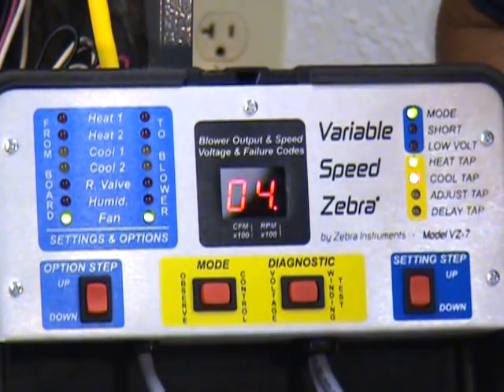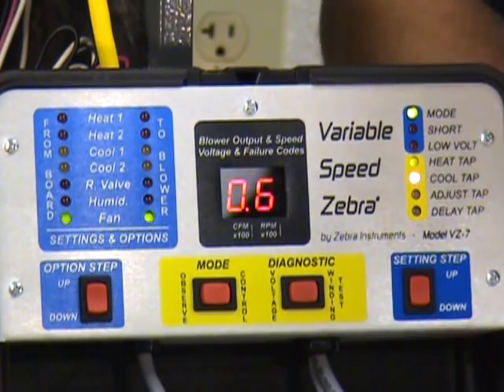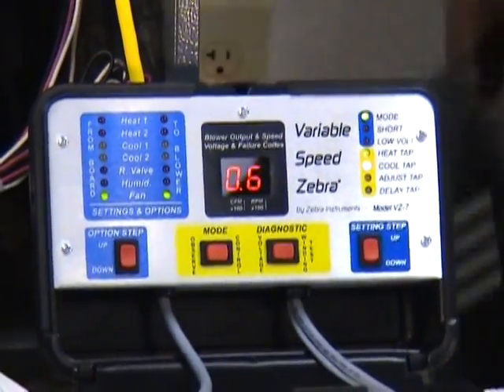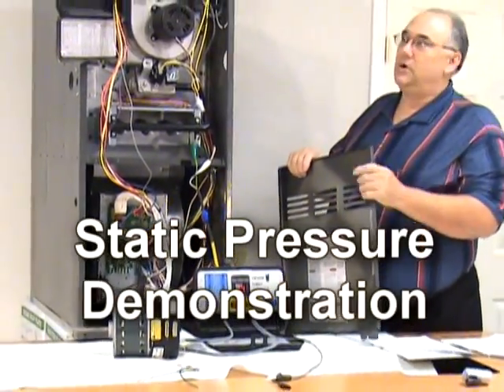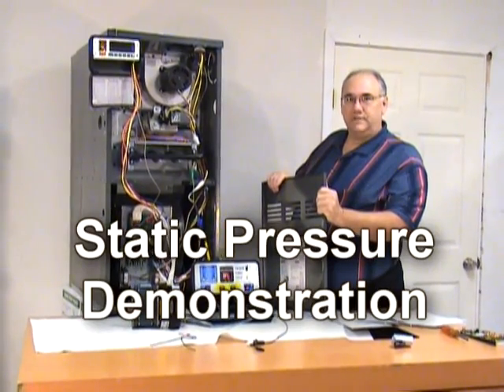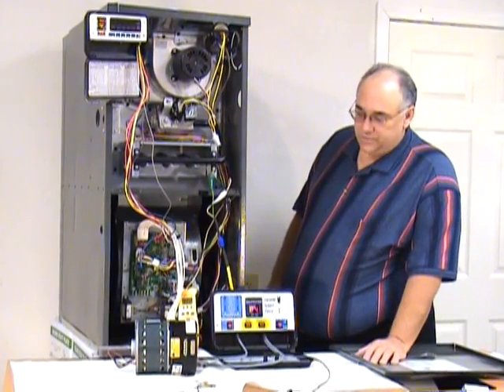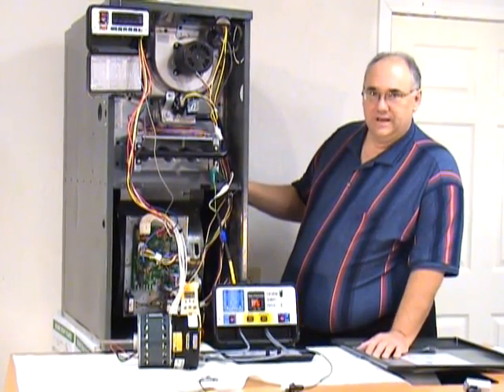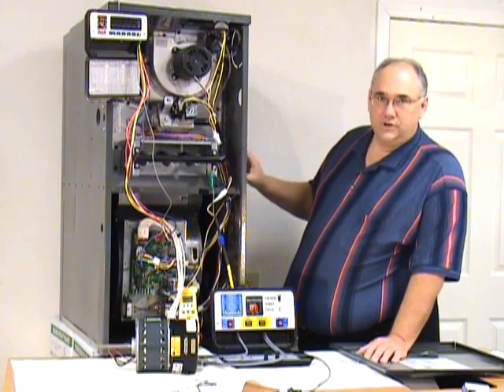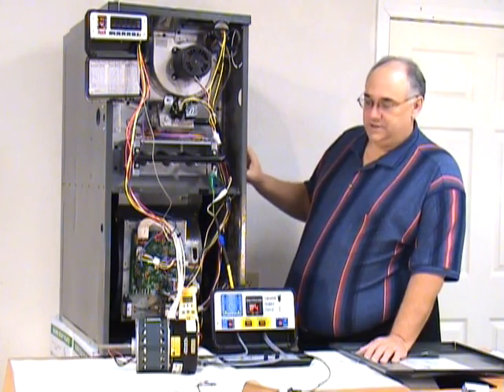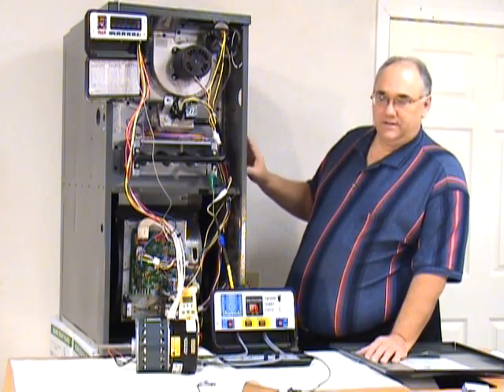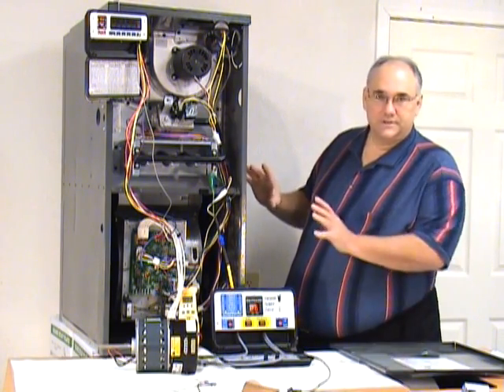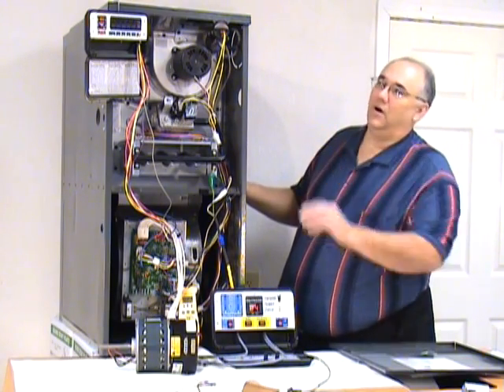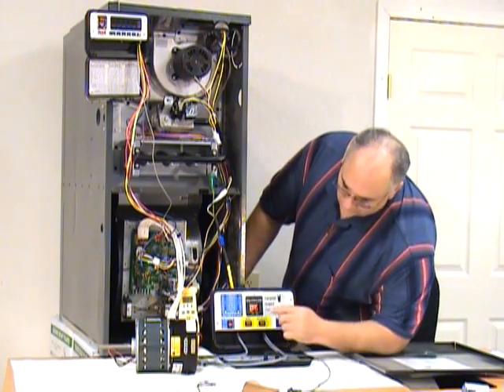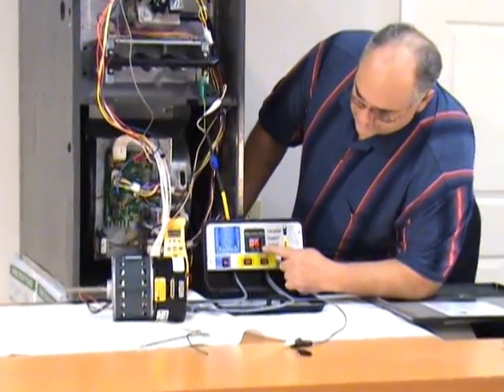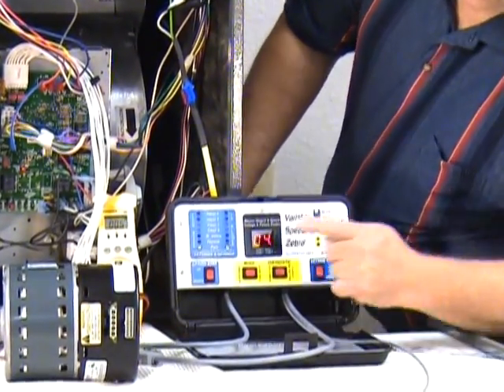One of the things that I love to show is how a variable speed motor works to maintain a CFM range. Depending on the external static pressure of your system, these motors will actually change speed, increasing or decreasing the RPM to maintain as close as possible the CFM that they're being told to maintain. For instance, we're on the fan only setting right now, and our variable speed Zebra is telling me that it's pumping 600 CFM and running at 400 RPM.